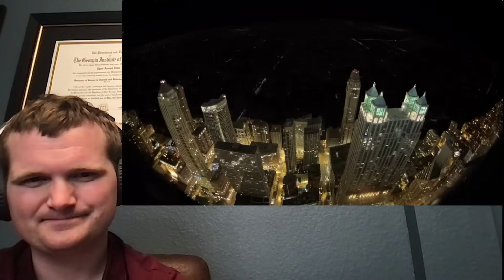That alone probably isn't enough to cause a large-scale blackout of the power grid, but don't forget about E3. EPRI found that the third part of an EMP could lead to regional blackouts encompassing multiple states because of transformer core saturation and imbalances between supply and demand of electricity. And you'll see those in things like substations and switchyards, more so than probably any other component.